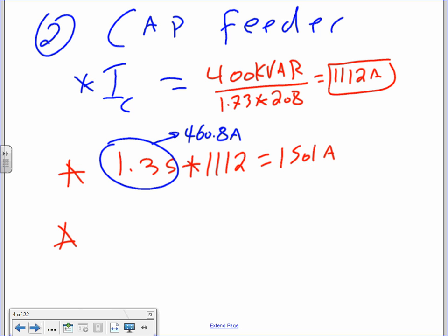Why not 1.25? 1.25 is for continuous load. These are continuous load plus they charge and discharge, so they abuse the conductors more. You need to up them a little. Okay. The rest is history, gentlemen. You can't find a conductor for 1501. It has to be a custom designed conductor for you. That's almost 1500 amps. That's a lot of amps. So what do you do? You parallel.